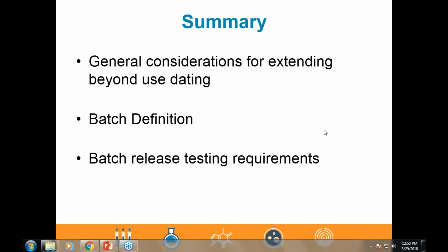Whereas endotoxin, as Brian had mentioned earlier, it doesn't matter if they're alive or dead, the endotoxin test is going to find them, right? So if something in that example did happen where it was endotoxin-free at the beginning, organisms penetrated, proliferated, and then died, they would not show up in the sterility test, but your endotoxin test would pick that up.